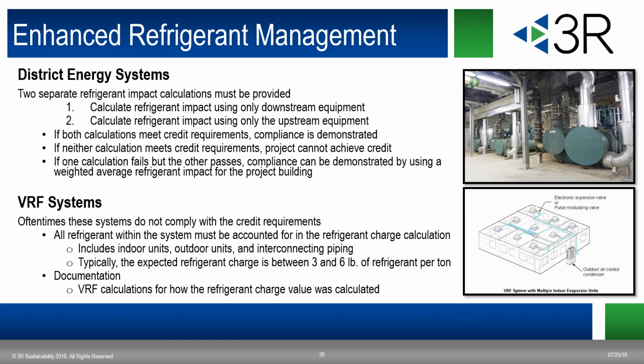The other special case is VRF systems, which are much more commonplace than just a few years ago. These systems may or may not comply with the credit requirements because they're refrigerant heavy, and all refrigerant in the system must be accounted for, including indoor units, outdoor units, and all interconnecting piping. Typically the expected refrigerant charge should be between 3 and 6 pounds of refrigerant per ton.